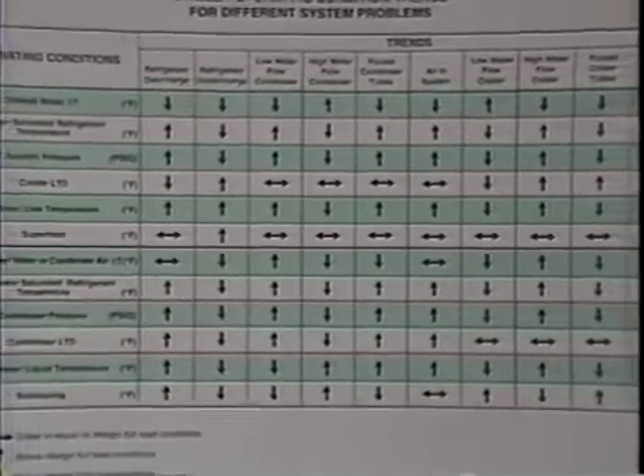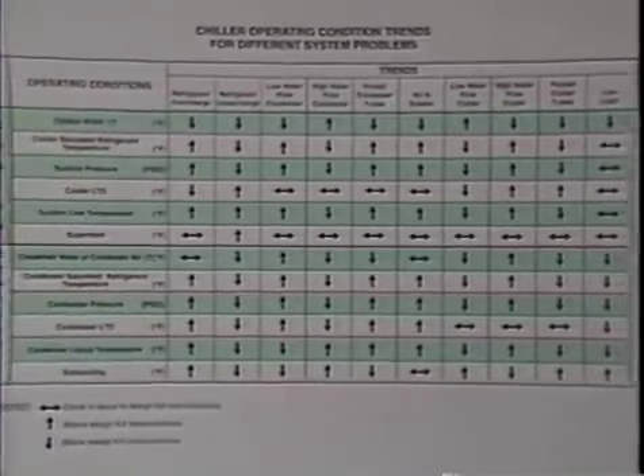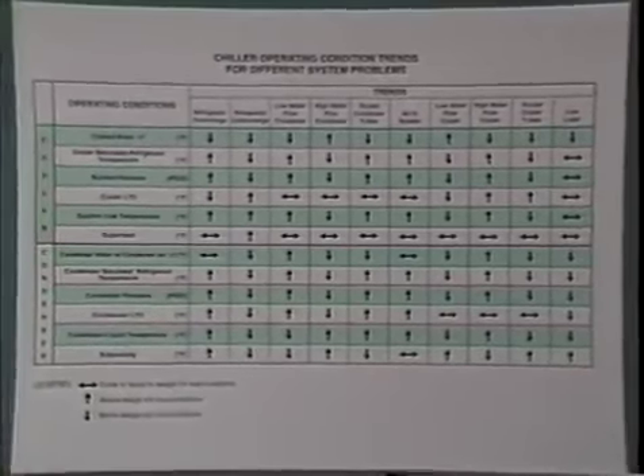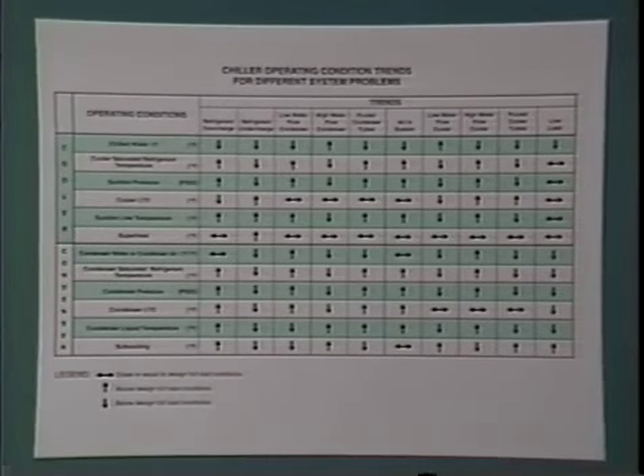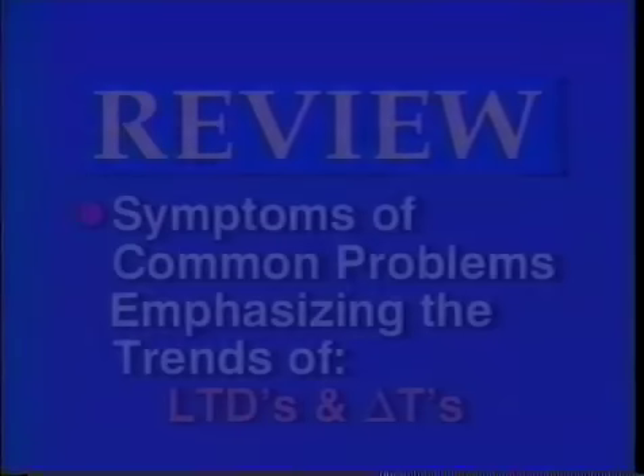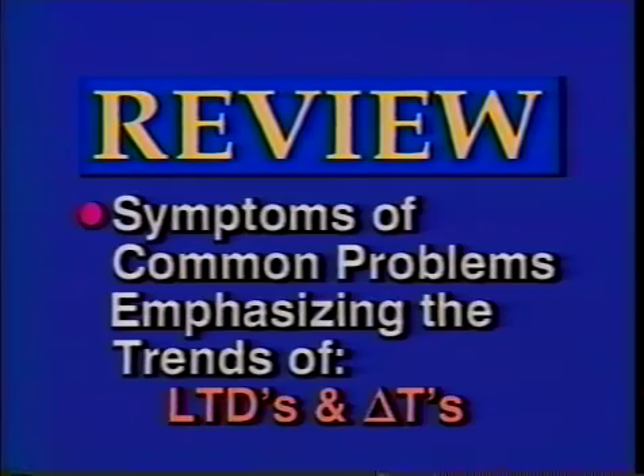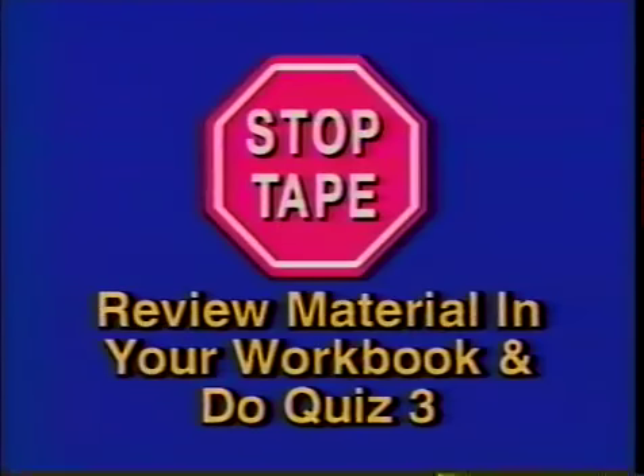So, whether you are troubleshooting a water-cooled or an air-cooled condenser, the trends of the symptoms of each type are basically the same. A chart is provided in the back of your workbook for your reference on operating condition trends for different system problems. In this section of the program, we discuss the symptoms of common problems, emphasizing the trends of the LTDs and delta T's. Now stop the tape, review the material in the workbook, and do quiz 3.